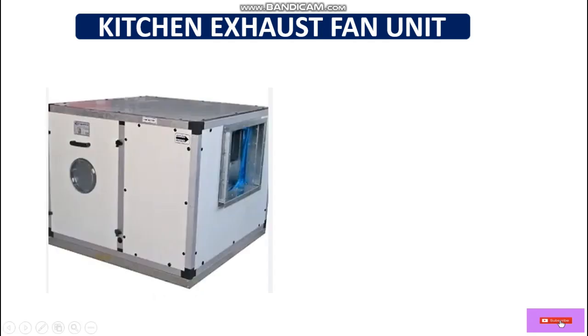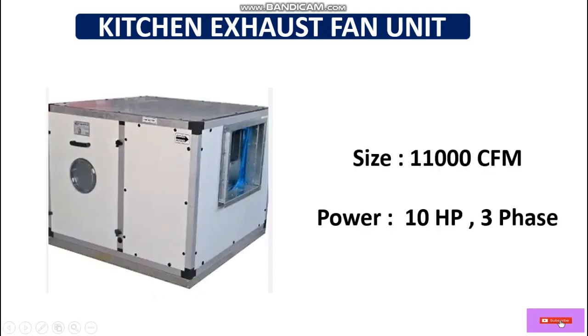So here we are going to calculate the contactor size for a kitchen exhaust unit star delta starter. This is the kitchen exhaust fan unit. If we talk about its capacity, the size is 11,000 CFM and power consumption is 10 HP.